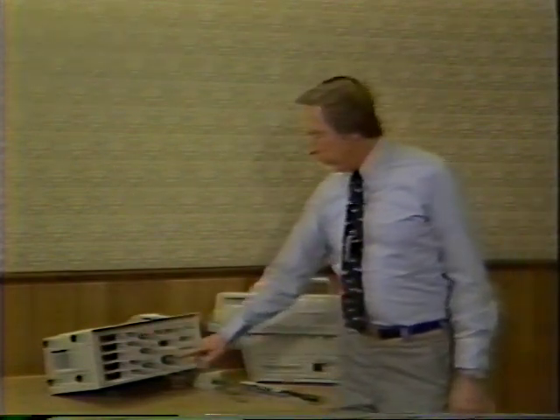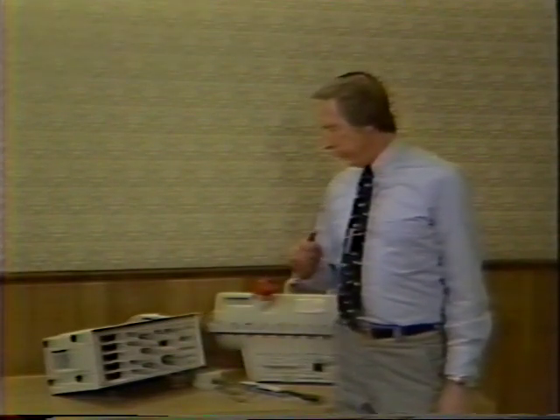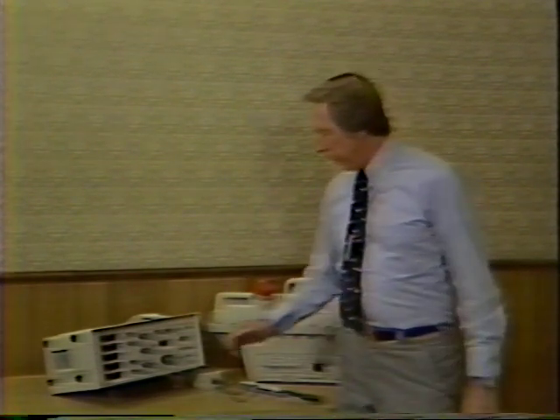The next control is the trigger level. This establishes the level on the pulse where we're going to trigger the digital clock, or where we're going to measure time. In the single phase mode, we would prefer to do it at the 10% level, in that we would get just above the level of grass. In three-phase, it's an entirely different situation.